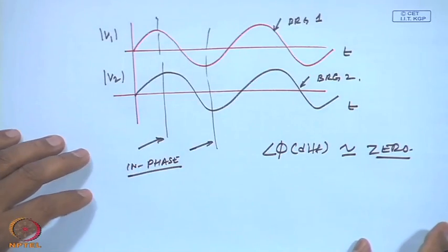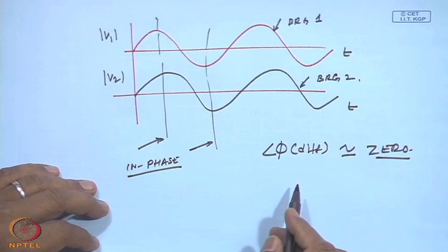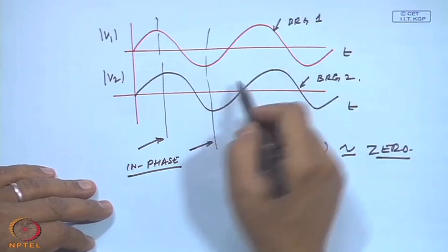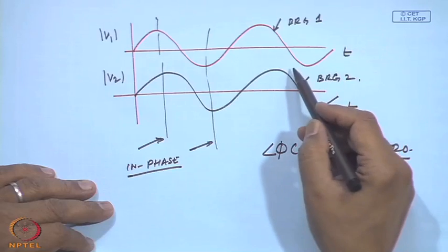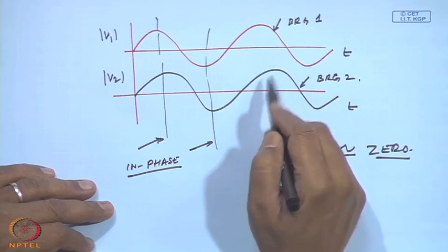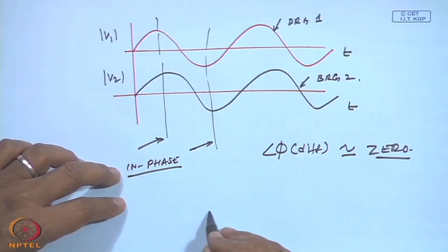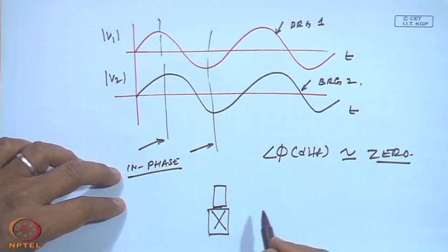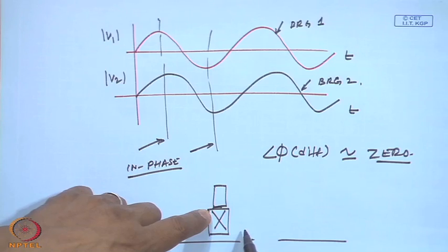It's nice to tell it in notes, but once you go to the field to measure, no system is perfect. When I drew a sinusoidal, if I show you an unbalanced time history of a signal, it is no way close to this, because in a machine everything is mixed up. Now, this sensor which you put on the bearing measures a lot of things. This measures the bearing vibrations, this on top of the unbalances.